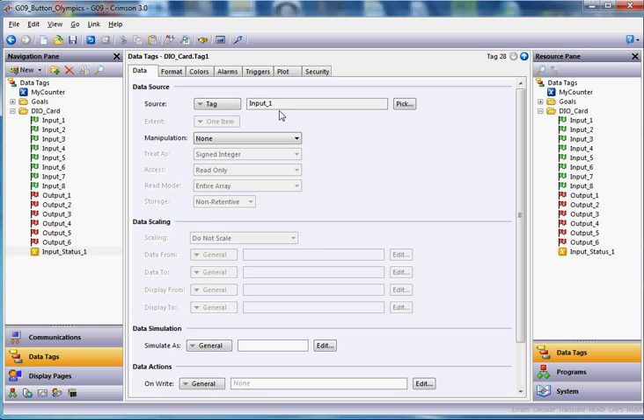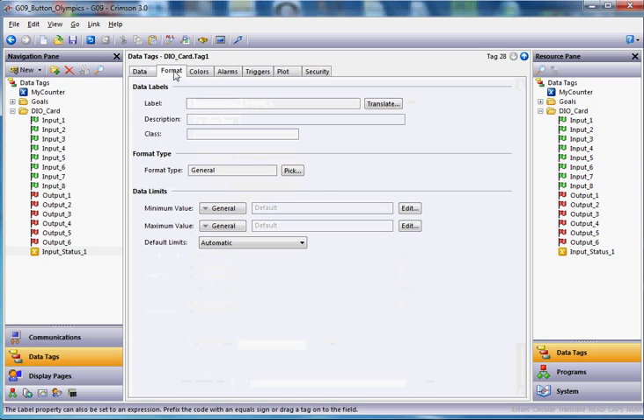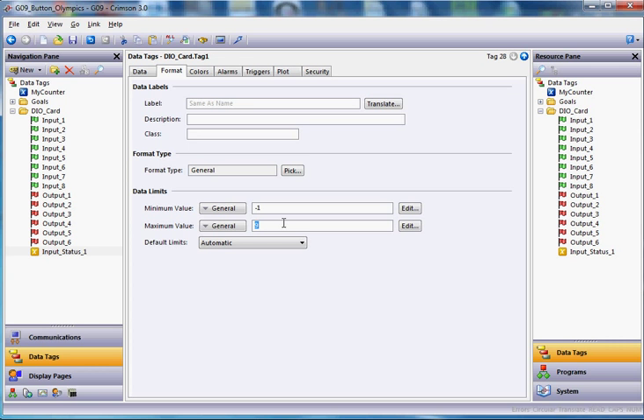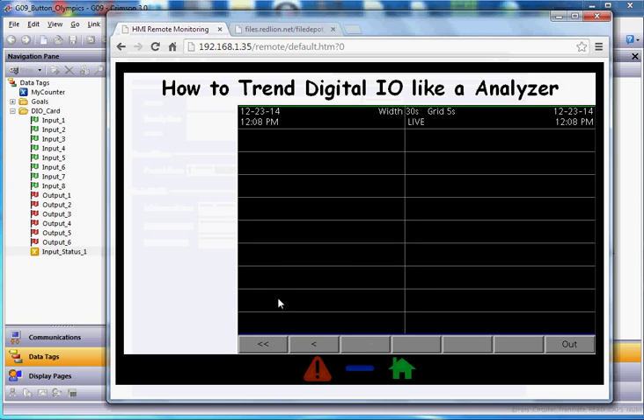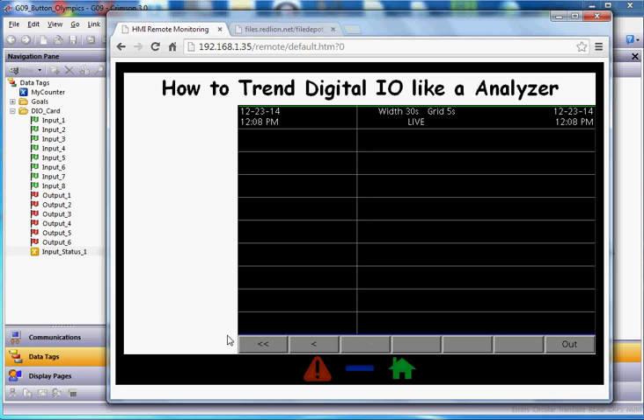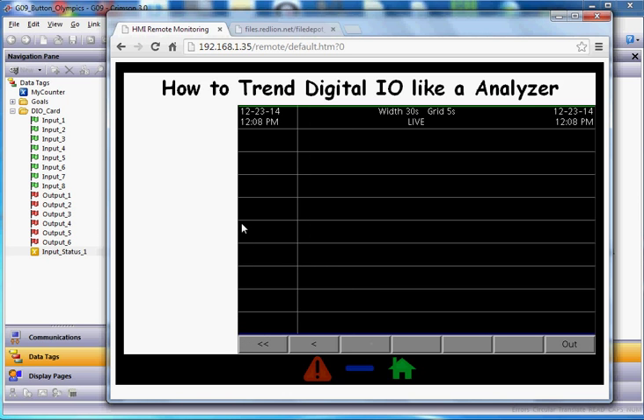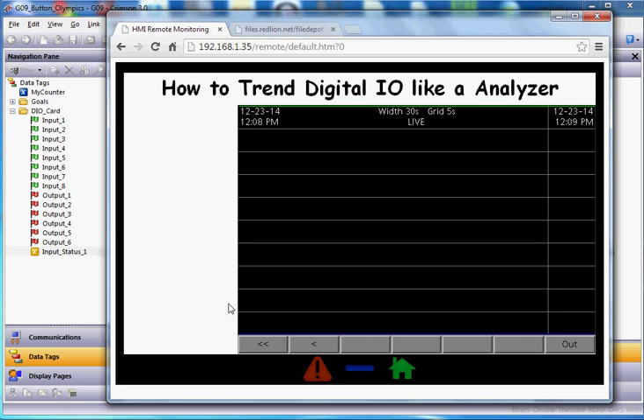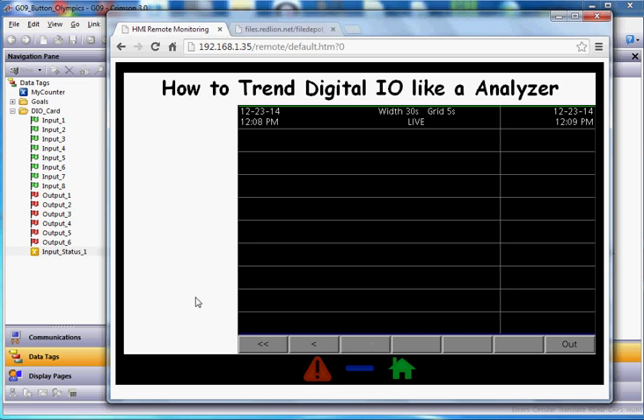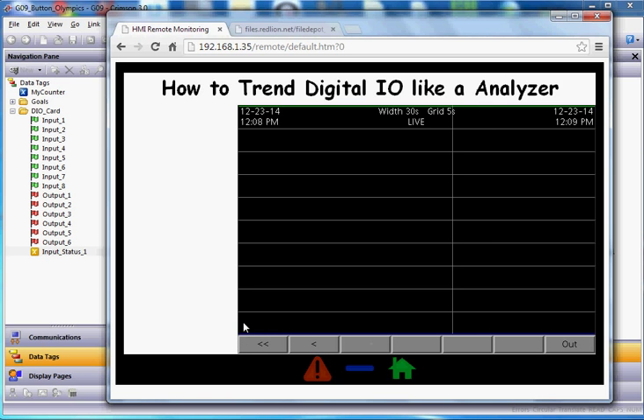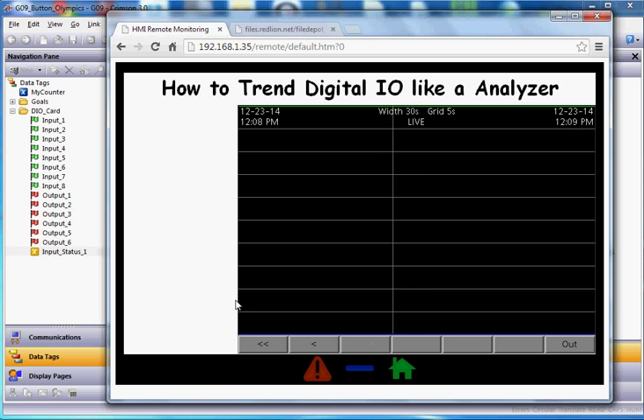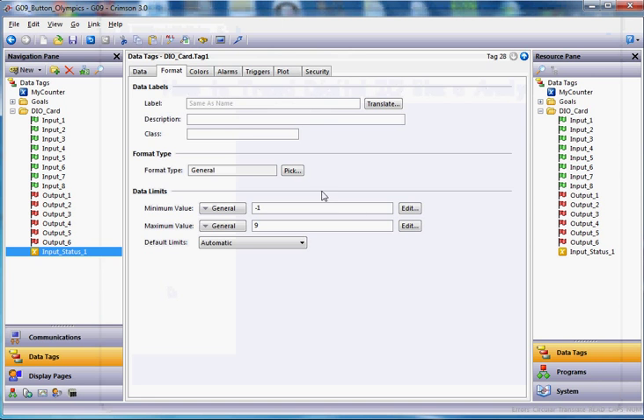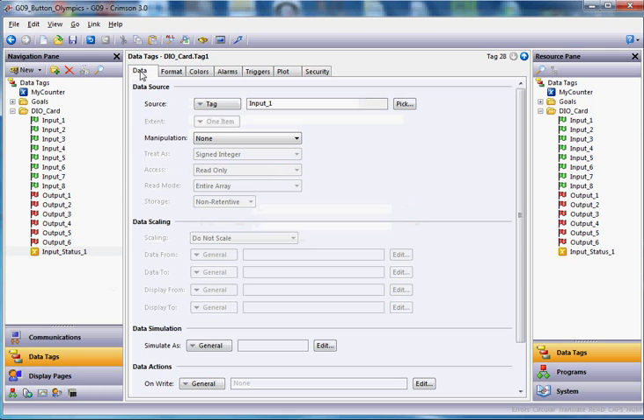Now, if I plot this on my trend viewer, currently it's going to go between, well, zero and infinity because I don't have any limits set up on this guy. So I'm going to go here to the format tab. And I'm going to say the format on this is going to be negative one to nine. It's going to sound weird. Negative one to nine. That's a span of ten lines. What I'm getting at here, let me go back to my browser. I've got ten of these markers going up here. So this bottom line right here would represent negative one. This would be zero, one, two, three, four, five, six, seven, eight, nine is the top. What I want to have happen is I want that channel that I just did to reside right in this spot right here. So this is negative one here to zero. So by default, that guy is going to go from zero to one. It should take this location here. So we'll leave this okay. That looks good there.